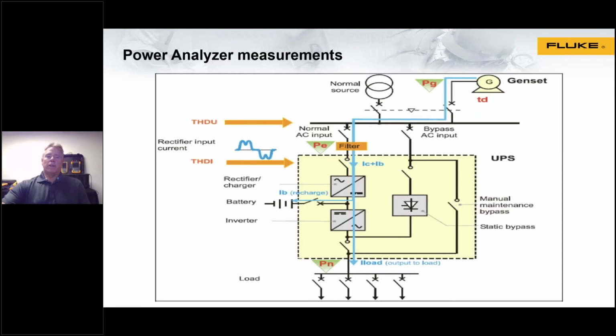Here's a diagram of a typical contingency supply system at critical installations. So what we're going to be looking at or examining is how by using a power analyzer, you can actually perform proper commissioning, maintenance on an ongoing basis, or troubleshooting, whatever that period is, monthly, quarterly, kind of depending on the scenario after commissioning.